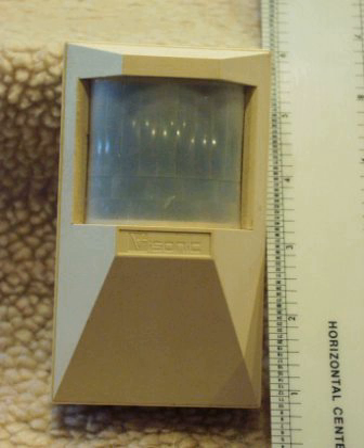Topic: Placement. Manufacturers recommend careful placement of their products to prevent false alarms, i.e., any detection not caused by an intruder. They suggest mounting the PIRs in such a way that the PIR cannot see out of a window. Although the wavelength of infrared radiation to which the chips are sensitive does not penetrate glass very well, a strong infrared source, such as from a vehicle headlight or sunlight, can overload the sensor and cause a false alarm. A person moving on the other side of the glass would not be seen by the PIR. That may be good for a window facing a public sidewalk, or bad for a window in an interior partition.